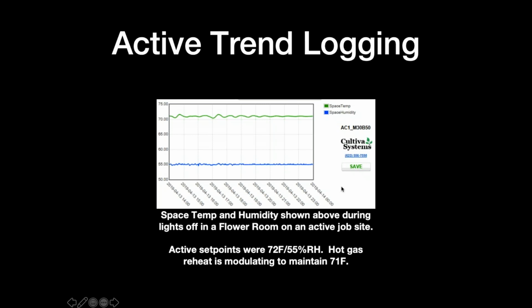All of these set points are field adjustable by the grower, but like I said, you want to make sure that you get the proper design parameters from that grower, because if they come in later and decide, oh, we want to lower the temperature and we want to lower the relative humidity, it makes it very difficult because those plants are still putting off a tremendous amount of moisture. And when you lower that temperature and humidity that you're trying to maintain in the room, the ability of the equipment to remove moisture is substantially reduced.